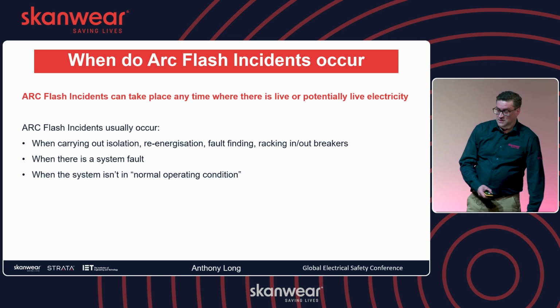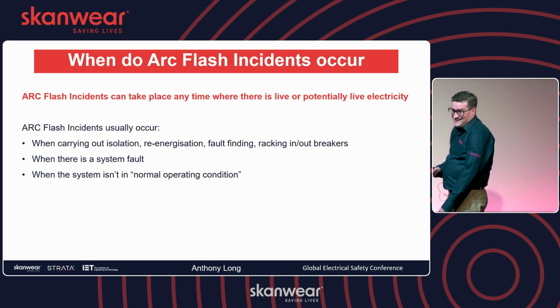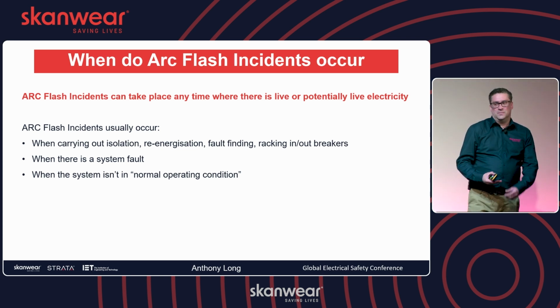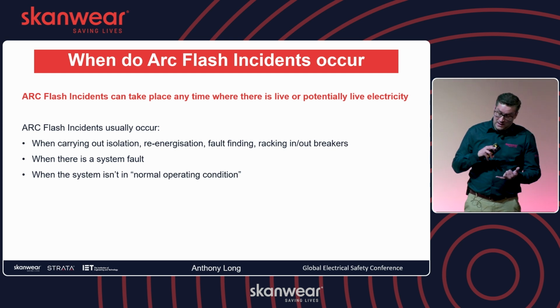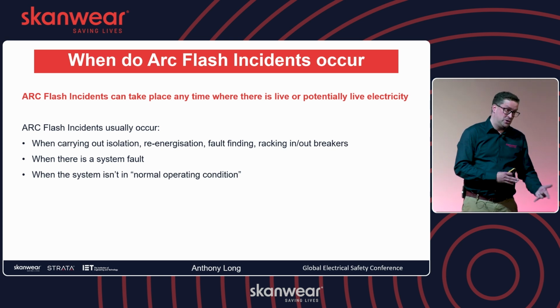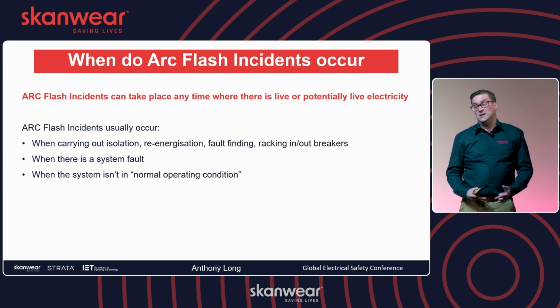This is a term, normal operating condition, referred to in NFPA 70E, I believe it came in the 2018 edition. It's basically referring to something not in its normal operating condition - so if you're commissioning something, it's not in normal operating condition. If you've not got a service and maintenance history, it's not in normal operating condition.